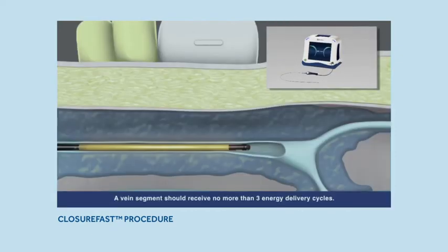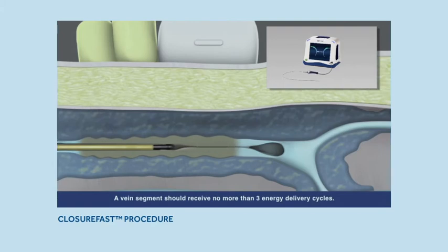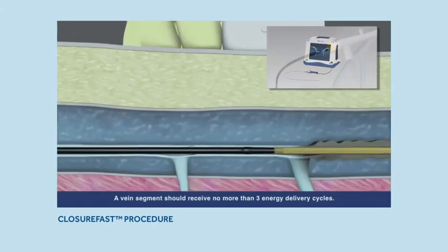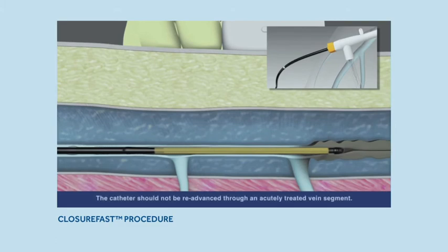Temperature control is a critical aspect of the procedure. The Closure RFG generator is designed to ensure the energy delivered to the catheter is consistent and controlled. For a successful procedure, the catheter uses segmental ablation technology to deliver precise, uniform radiofrequency energy to the heating element.